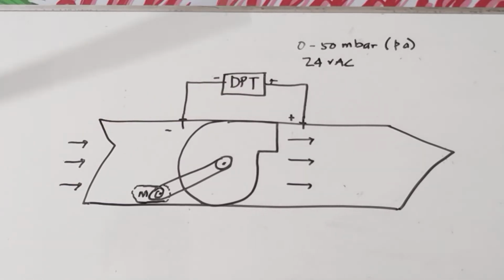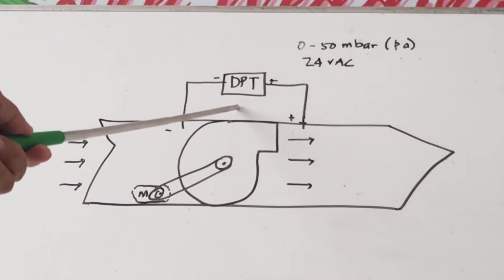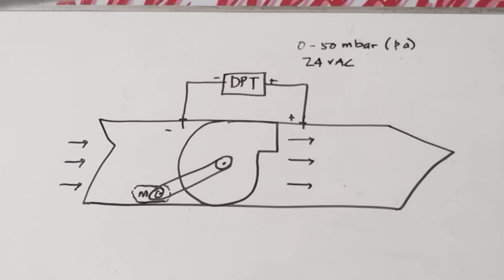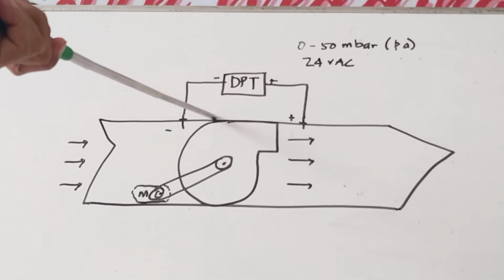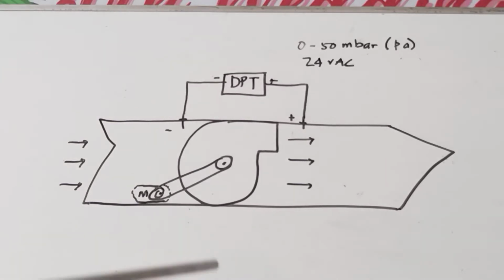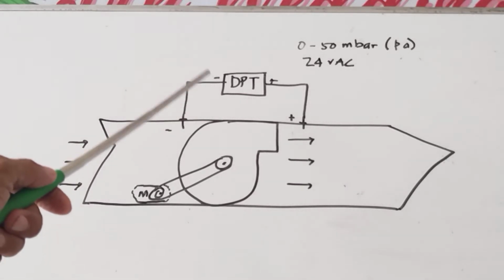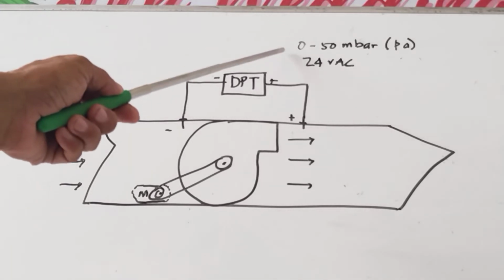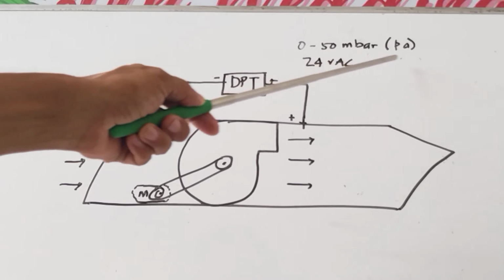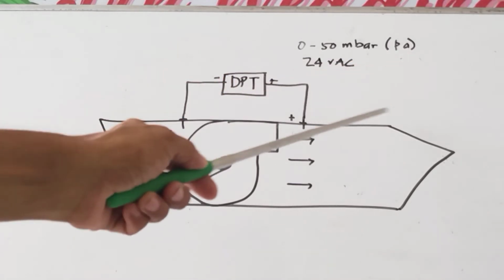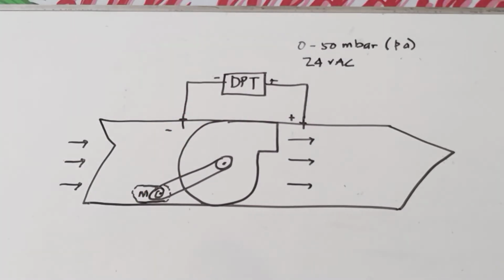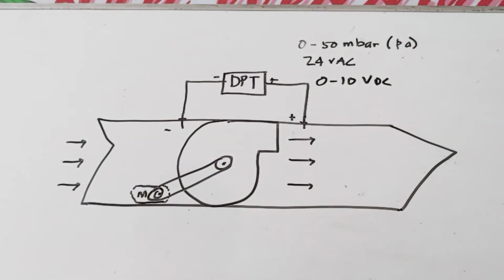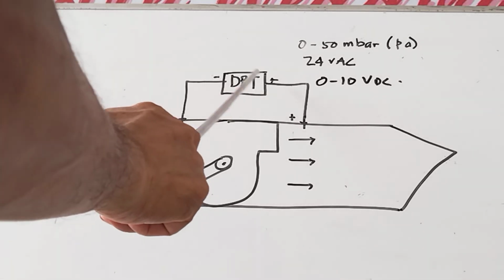Then provide the necessary cable to provide power supply and to get the control signal that will be produced by this differential pressure transmitter. Okay, so this is how you are going to install the differential pressure transmitter across the fan if you want to know exactly what is the differential pressure across the fan. Okay, now the range is 0 to 50 millibar. Now 50 millibar is equivalent to 5000 Pascal. Okay, now the power supply is 24 volts AC. Okay, then the control signal is 0 to 10 volt DC. Okay, so this is the signal that will come out of this DPT sensor.